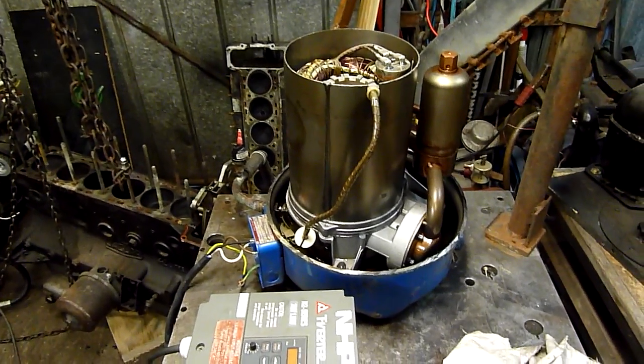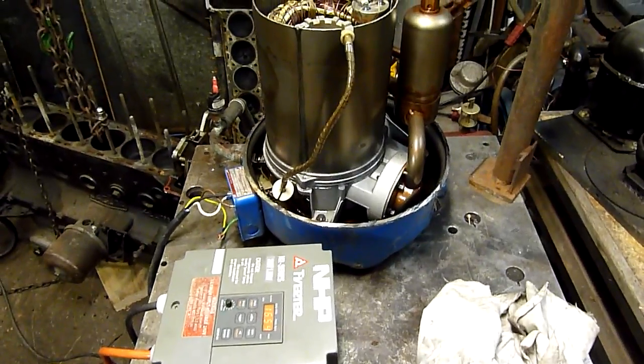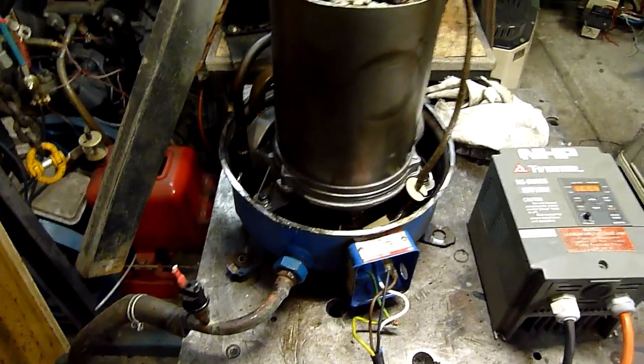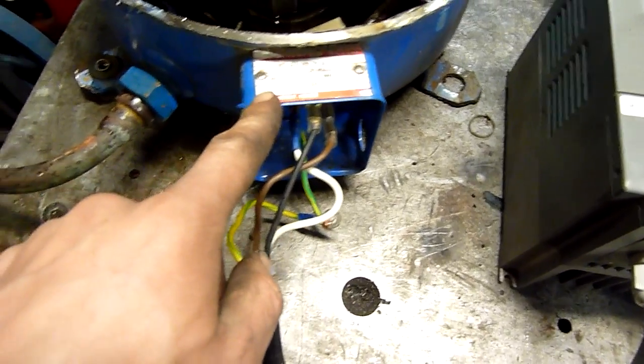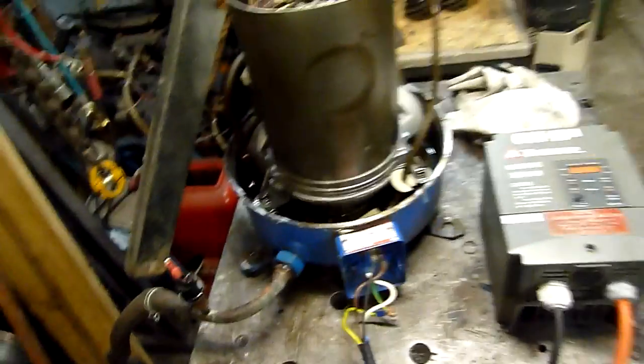G'day folks, it's time to give this French-made Maneurop two-cylinder air conditioning compressor a bit of a run. This one came out of the big condensing unit I had outside my workshop for a while. Rated at 380 to 460 volt three-phase, 15 amps running maximum, 63 amps locked rotor. It's a MT64 MM4A, made in France by Maneurop. It's reasonably old — a mid-90s model, a bit different to the newer ones that I've scrapped.